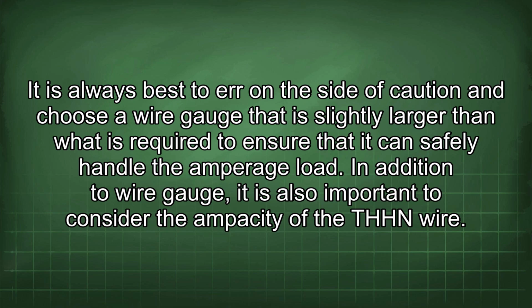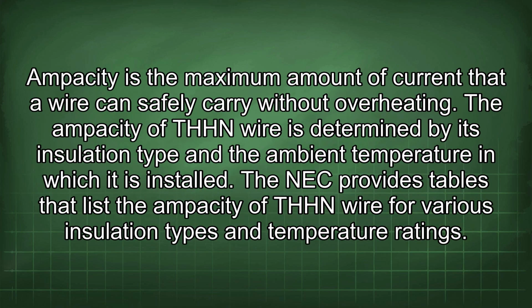In addition to wire gauge, it is also important to consider the ampacity of the THHN wire. Ampacity is the maximum amount of current that a wire can safely carry without overheating. The ampacity of THHN wire is determined by its insulation type and the ambient temperature in which it is installed. The NEC provides tables that list the ampacity of THHN wire for various insulation types and temperature ratings.